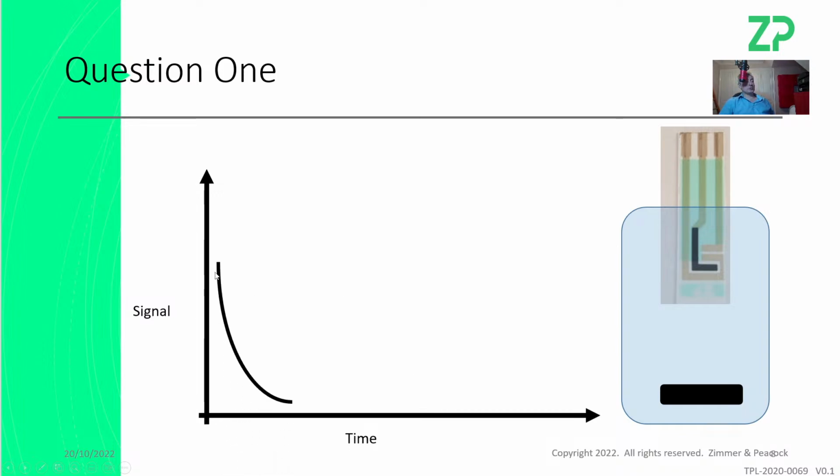The first thing we do is run 0 millimolar glucose on the sensor. We have this break-in time, and when it has plateaued, that's when we add an aliquot of quite concentrated glucose solution. This is the way we often do it in-house: start off at 0 millimolar, with the sensor in the beaker. There are a couple of videos that I will be showing later, related to question number 6, where you'll see Andre actually doing this.